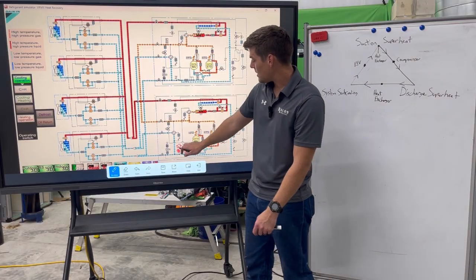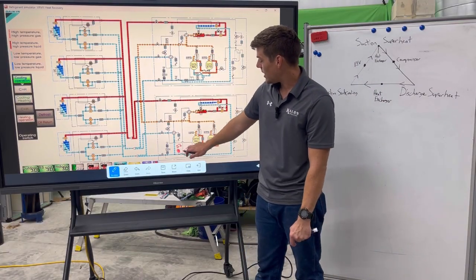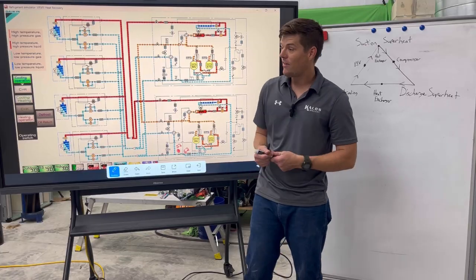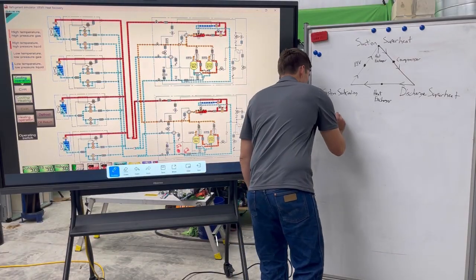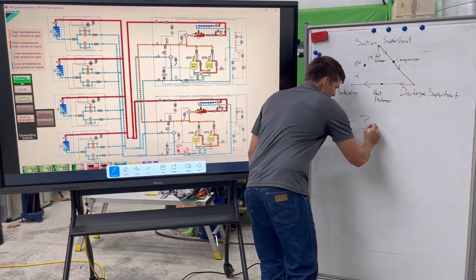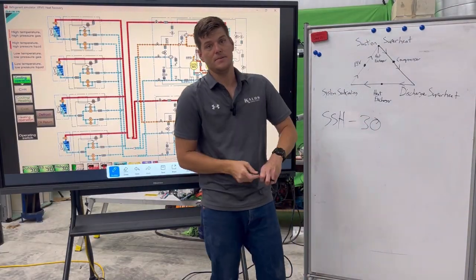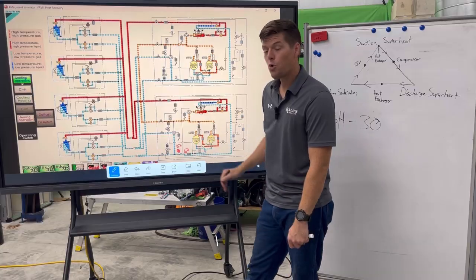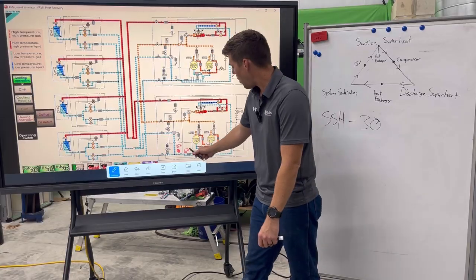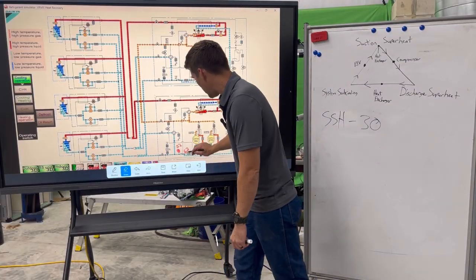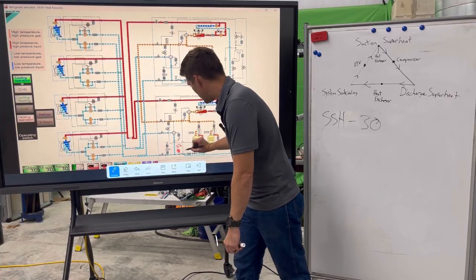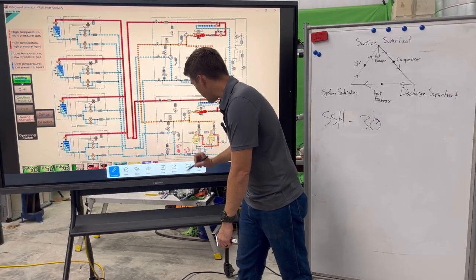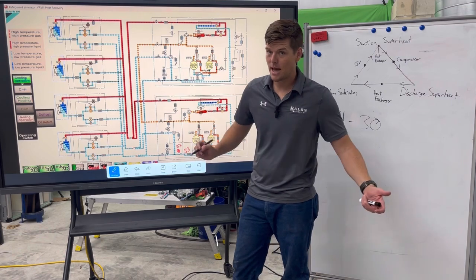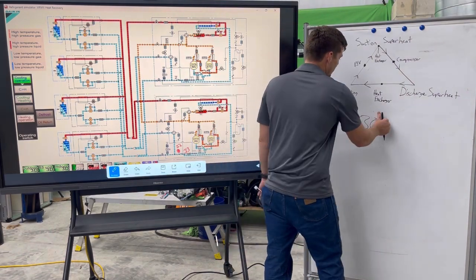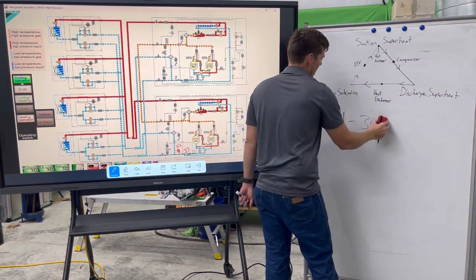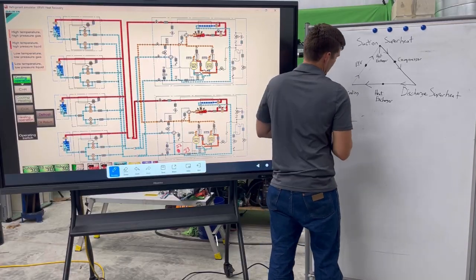Well, I know that because my saturation temperature is 32 and my line temp is 62, I have a suction superheat of, you guessed it, 30 degrees. Well, we just mentioned that. Okay, so we know what the quality of vapor is coming back to my compressor. Now, what if I come back in here and I say, let's say that this is 33 degrees on my suction temp, because it happens. Well, then that means that instead of having 30 degrees here, we have 1 degree of suction superheat.